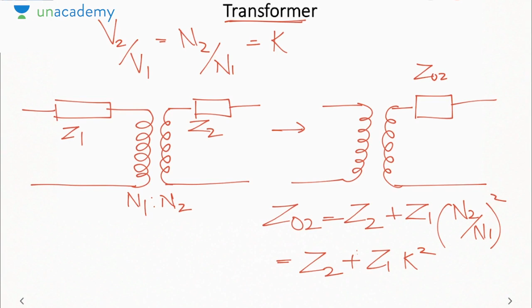Remember, here we are neglecting the shunt branches because the impedance or the no load current is negligible as compared to your full load current and the fault current. So we have to neglect the no load parameters.